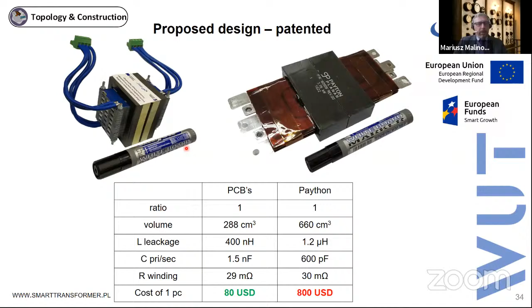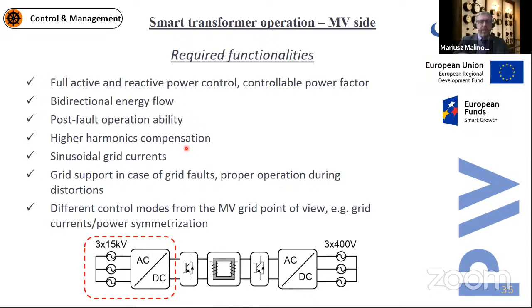But let's analyze some of the functionalities, because as I told you, the power electronics transformer is like a topology with simple control. But if we are thinking about the smart transformer, we should consider other functionality which is available for the system. For this additional functionality, we can distinguish full active and reactive power control. We have bidirectional energy flow, of course, post-fault operation, and higher harmonic compensation. We should provide sinusoidal grid current, and we can provide grid support in case of a fault. We can also use different control methods to make a symmetrization of the power.